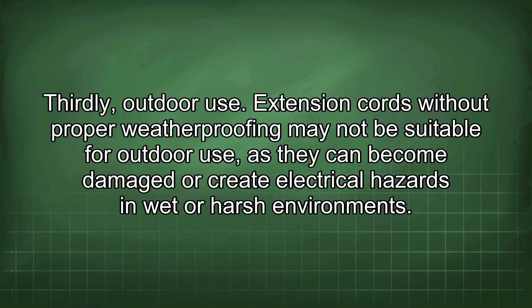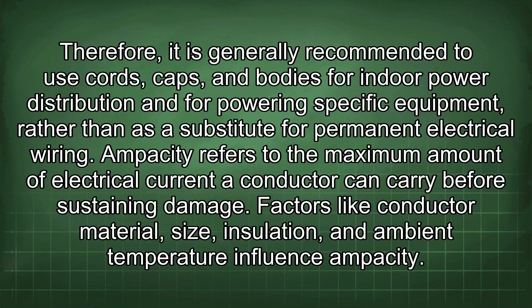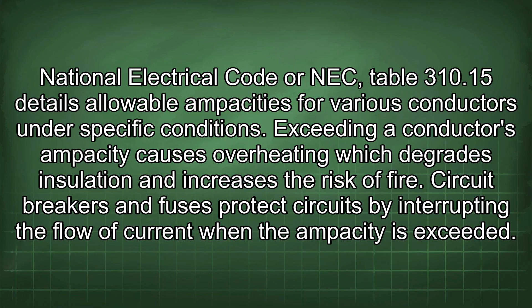Ampacity refers to the maximum amount of electrical current a conductor can carry before sustaining damage. Factors like conductor material, size, insulation, and ambient temperature influence ampacity. National Electrical Code, or NEC, Table 310.15 details allowable ampacities for various conductors under specific conditions. Exceeding a conductor's ampacity causes overheating, which degrades insulation and increases the risk of fire. Circuit breakers and fuses protect circuits by interrupting the flow of current when the ampacity is exceeded.